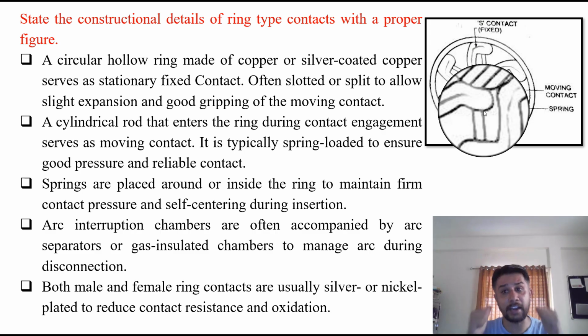To ensure good pressure and reliable contact, springs are placed around or inside the ring to maintain firm contact pressure and self-centering during the insertion, that is the moving contact inserting in the fixed contact. Arc interruption chambers are often accompanied by arc separators or gas insulated chambers to manage the arc during disconnection, because when the contacts are separated, the arc strikes between the fixed contact and moving contact. Both these male and female ring contacts are usually silver or nickel plated to reduce the contact resistance and oxidation, and due to that the arc is controlled. So this is the constructional detail of ring type contacts.